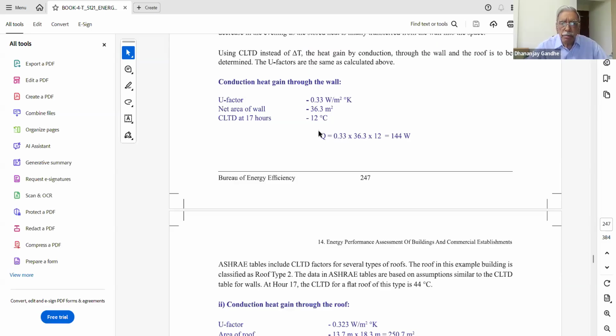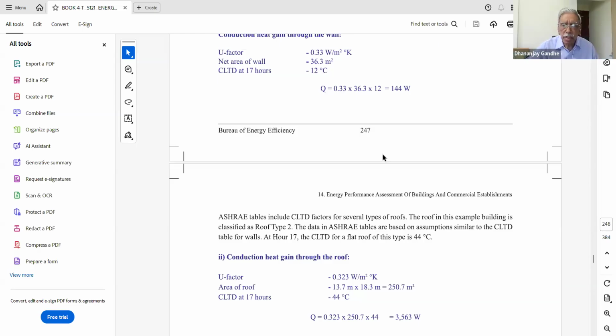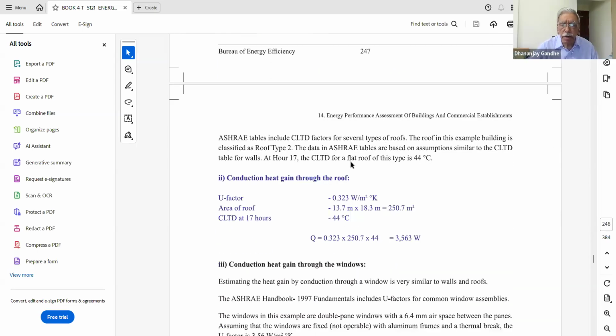So heat gain will be U factor multiplied by area of wall multiplied by temperature difference, which is the CLTD, the standard temperature difference, not the actual one, is equal to 0.33 into 36.3 into 12, it is 144. This is the heat gain, expressed in watts.